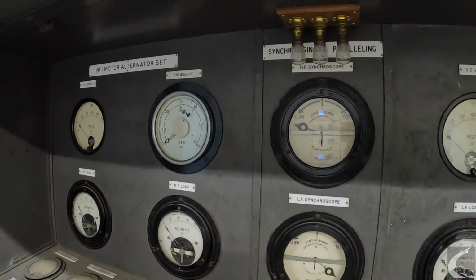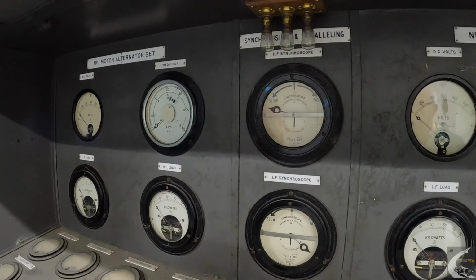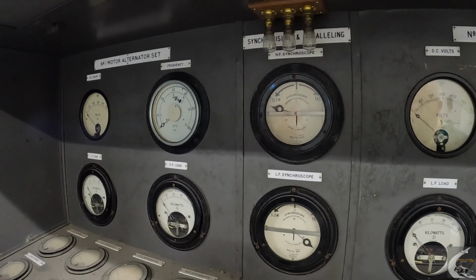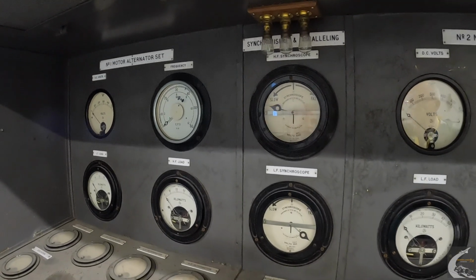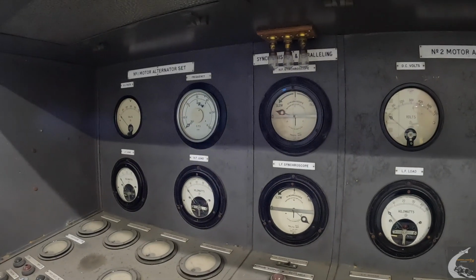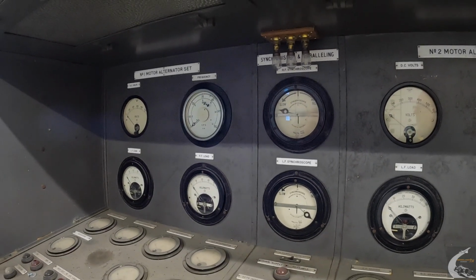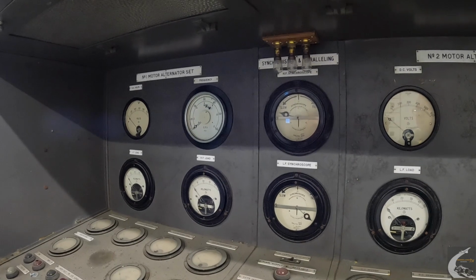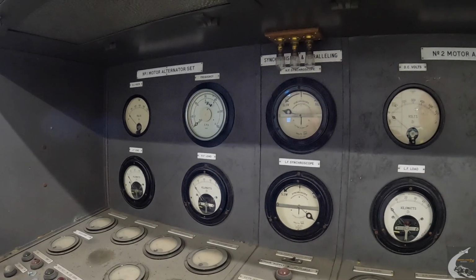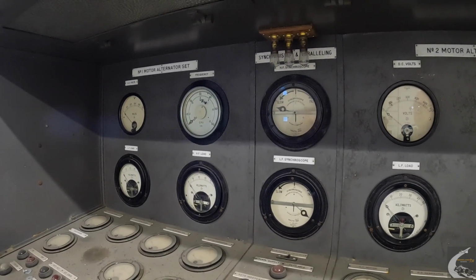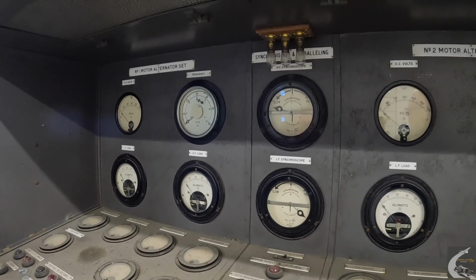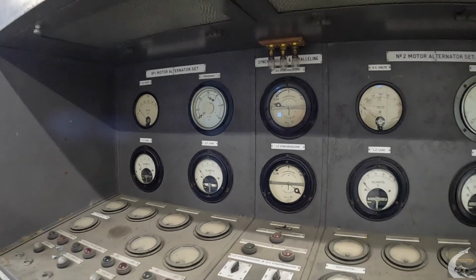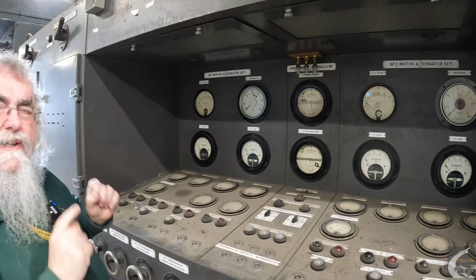Now if they're out of sync, basically these bulbs will be flashing together. As you start adjusting the speed, the bulbs will start flashing at a slower rate, and when you've actually got them properly in sync, the bulbs should go out, because you can detect much better whether the bulb is glowing at all or not.